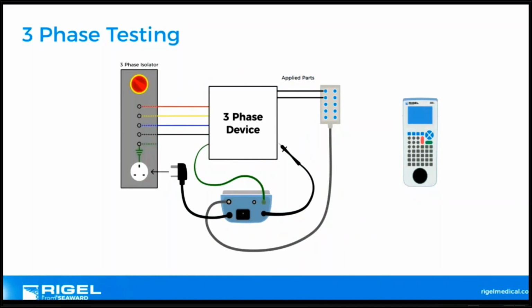Right, testing different scenarios. I'll keep this brief because we are running slightly over. You can use a 288 to do 3-phase testing. Bear in mind, if you are going to do any 3-phase testing, or fixed, it doesn't necessarily need to be 3-phase, it's just fixed, you can remove the earth here. But make sure that you're a competent engineer or you have the facilities or state's guidance to do this, because you need to be qualified as it's extremely hazardous to remove the earth.